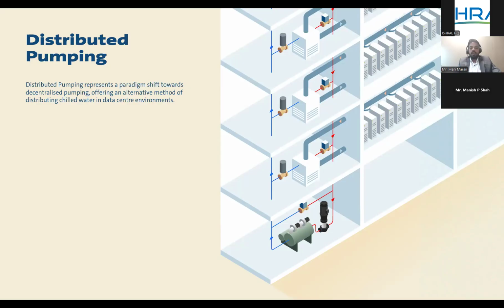In a chilled water system, a modulating valve is traditionally the way to control the flow in the system, right? Which in turn controls the cooling flow. That's how we've traditionally been doing chilled water distribution and addressing the cooling load for more than a decade, or even a couple of decades. But when a valve gets throttled, it creates a back pressure, which adds head to the pump, requires more power, and consumes energy to overcome this back pressure. That's what we see today as part of the traditional design.